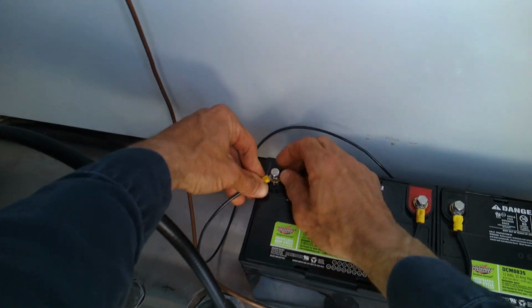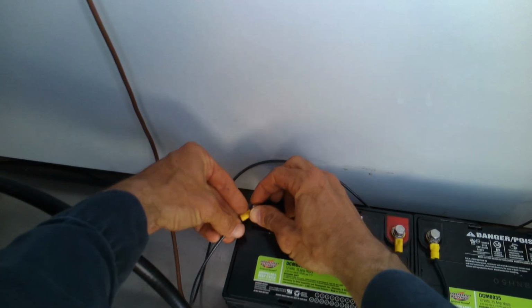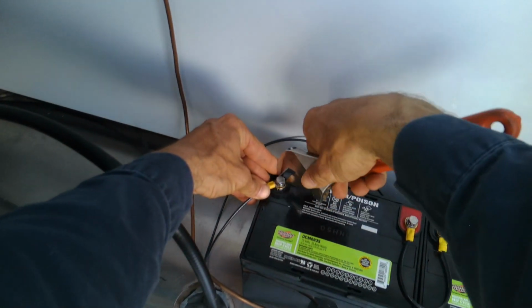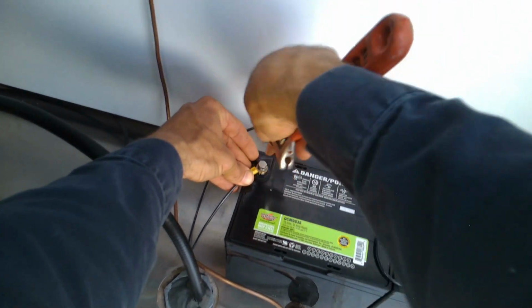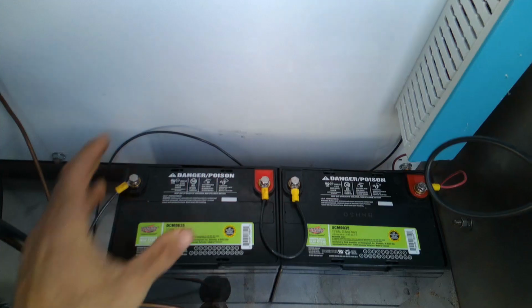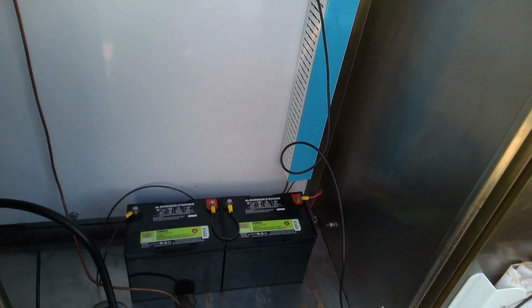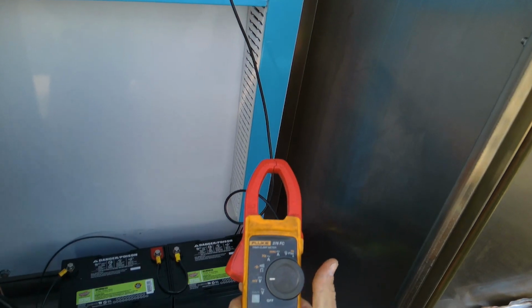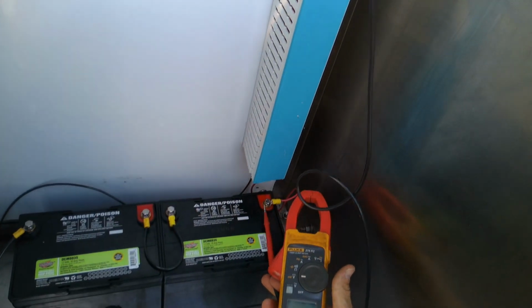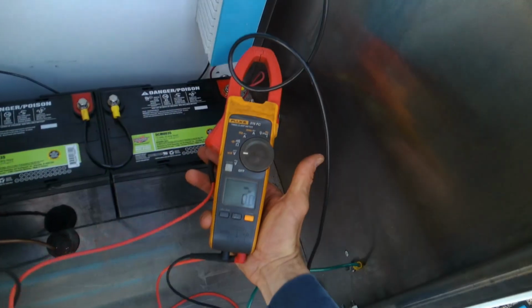Connect that on. Let's see. Volts DC. Positive there, volts DC. Negative 27. Perfect. Yeah, a nice high float voltage. A little bit high. All right, high enough.